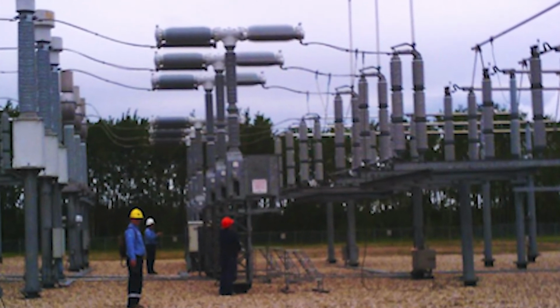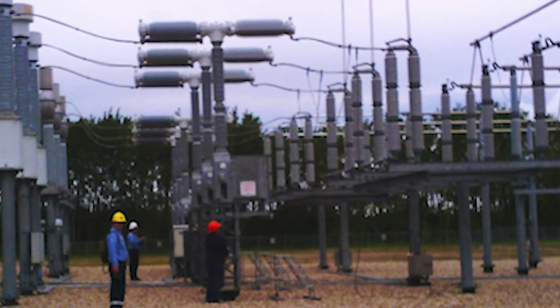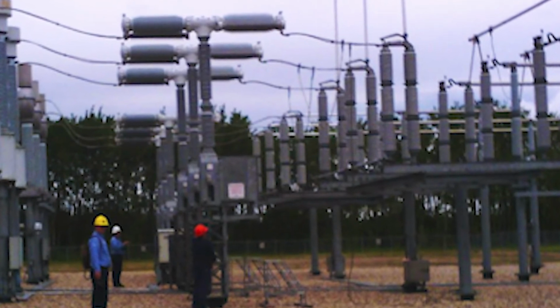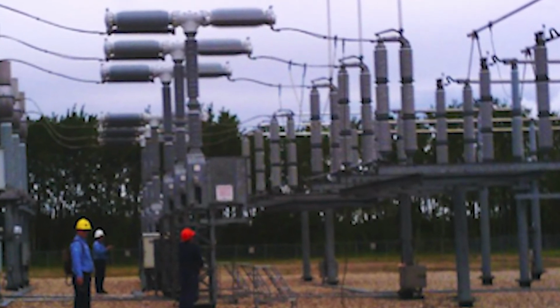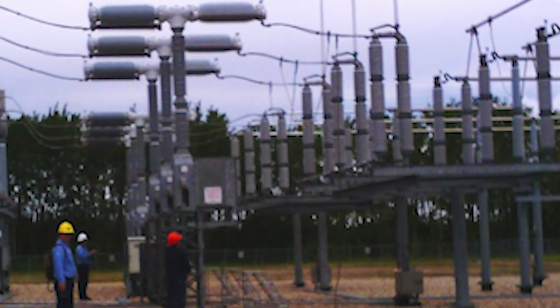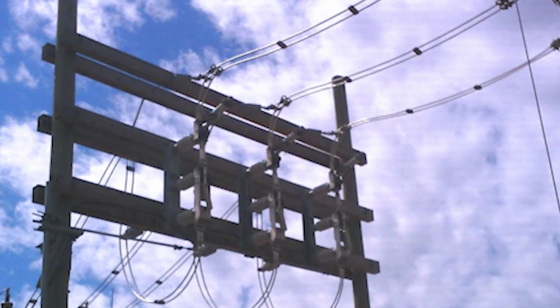You can see the grounds hanging down on the right hand side. They were doing a little bit of work at the time, and everything was open and grounded. We were looking for gas leaks with the GS77 on the bushings themselves. We moved to another substation just down the road.